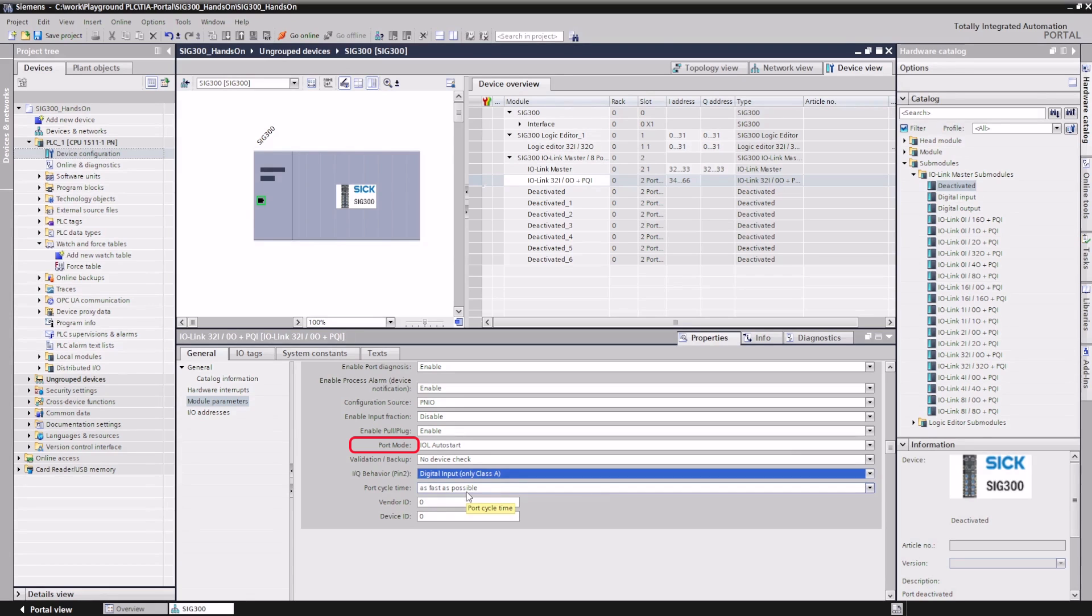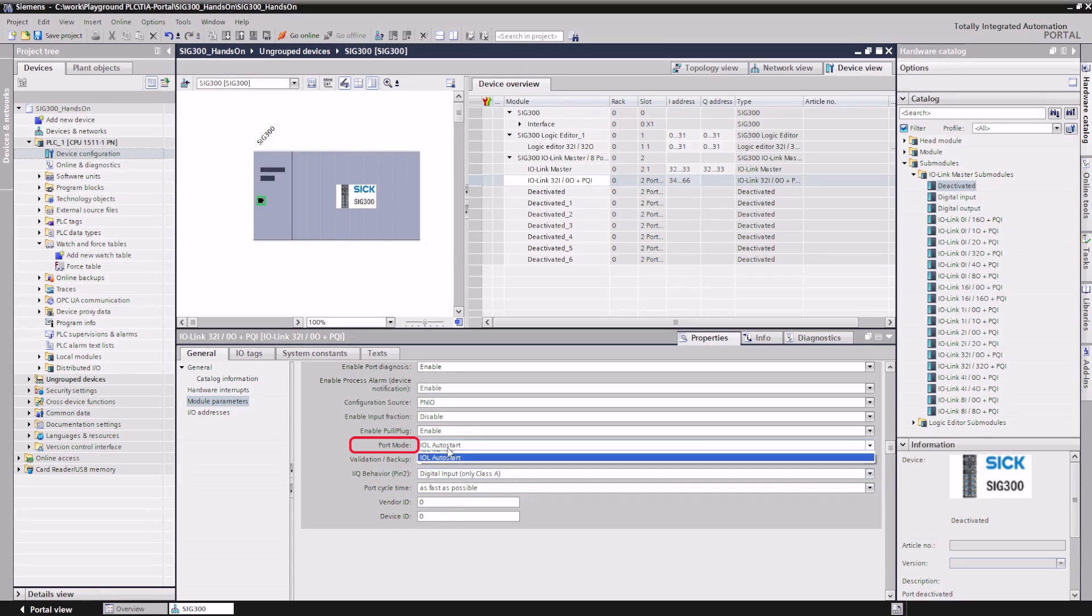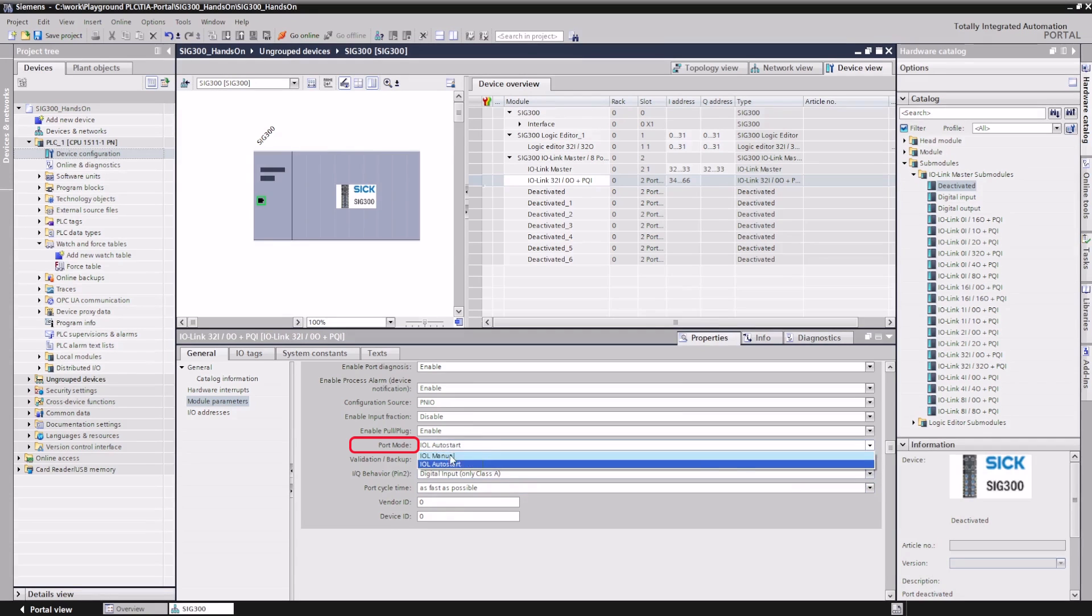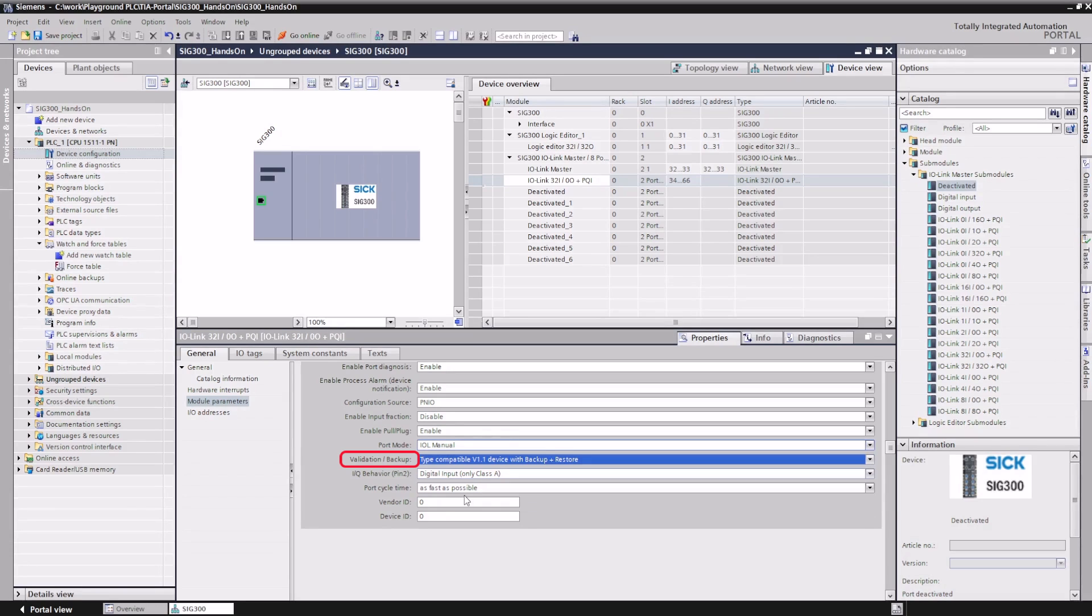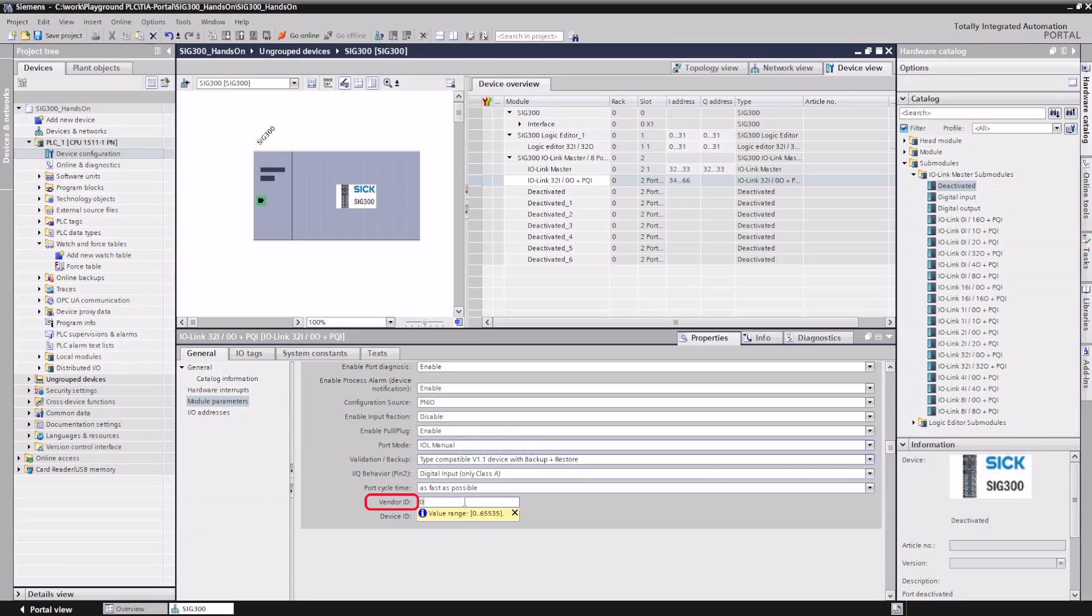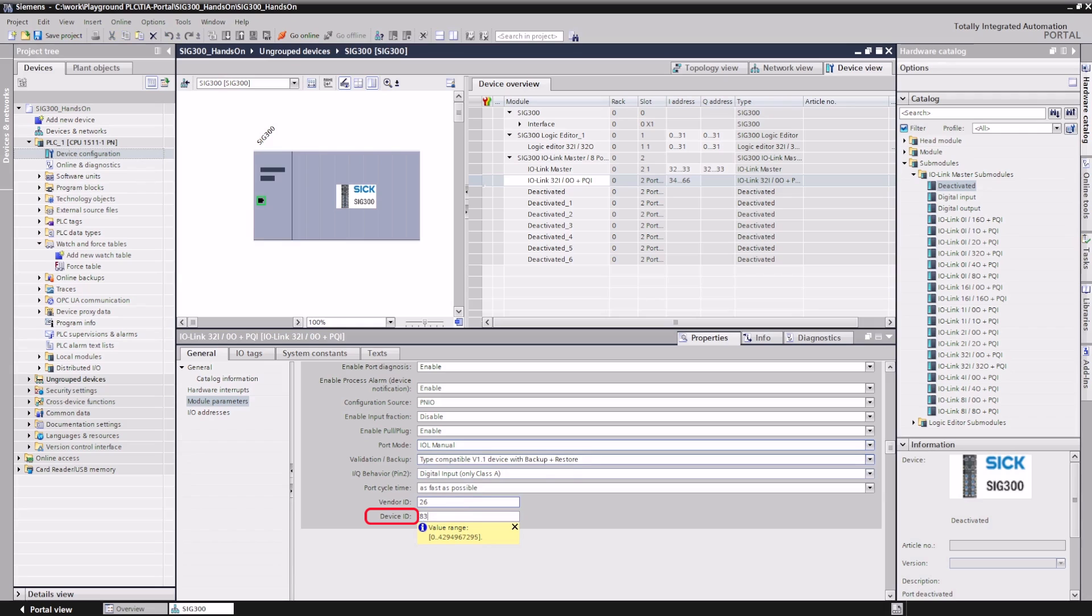To do this, it is necessary to switch the port mode to IOL manual and set validation and backup to type compatible V1.1, device with backup and restore. To enable the IO-Link master to check if the correct device is connected, the vendor ID and the device ID are also required. The information can be found in the operating instructions of the device.